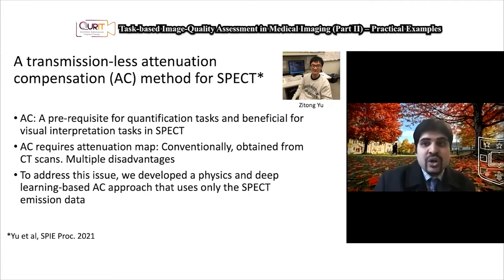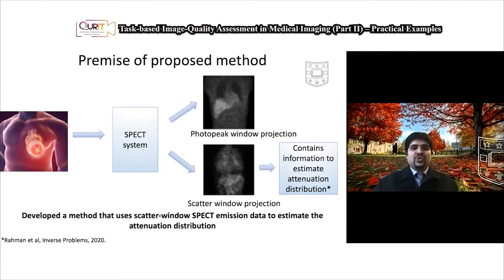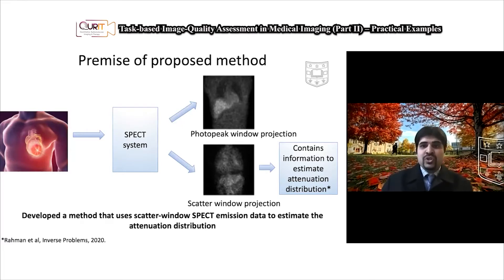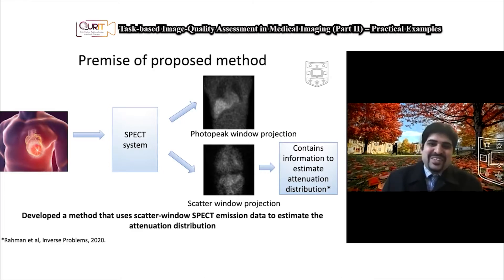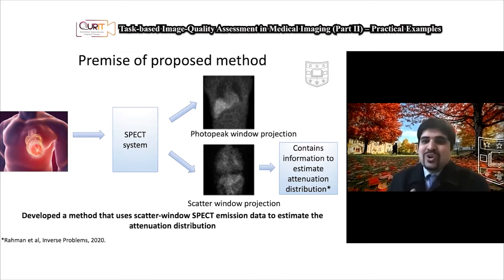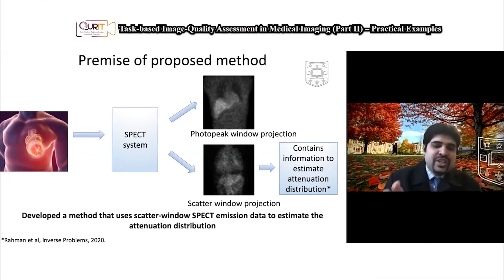In a SPECT system we obtain data in the photopeak window — photons acquired in a certain photopeak window, for example in technetium this would be 126 to 154 keV. This projection contains primarily unscattered photons, but also scattered photons. Then we have scatter window data, which primarily consists of photons that have been scattered. This data is often thrown away and discarded, but attenuation in SPECT is primarily due to Compton scatter — so these scattered photons may actually contain information to estimate the attenuation distribution.